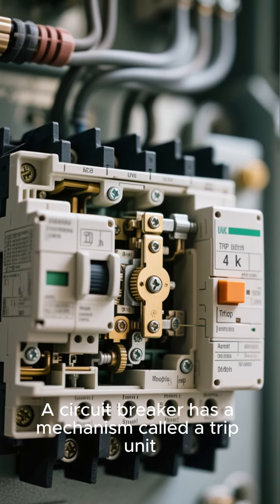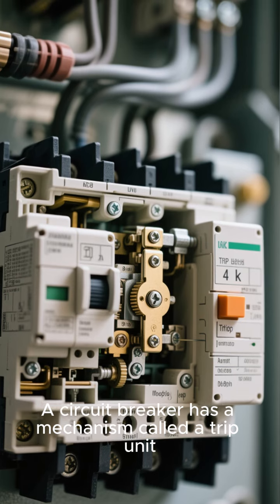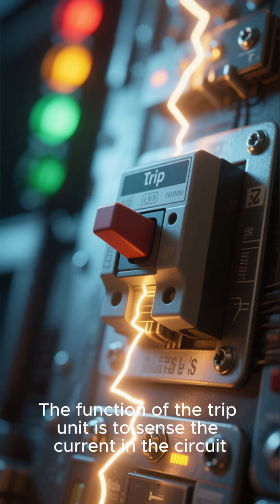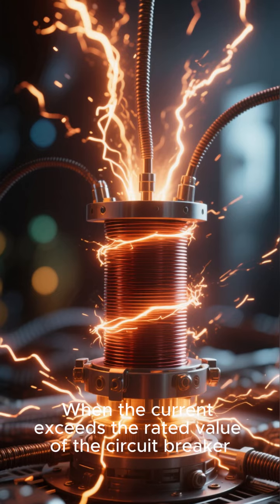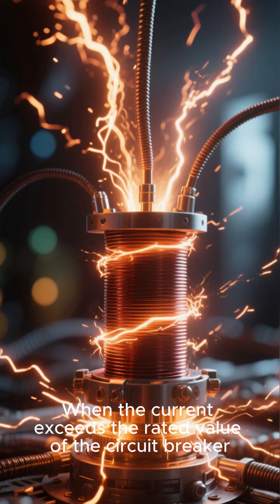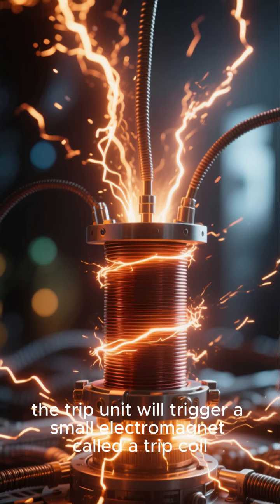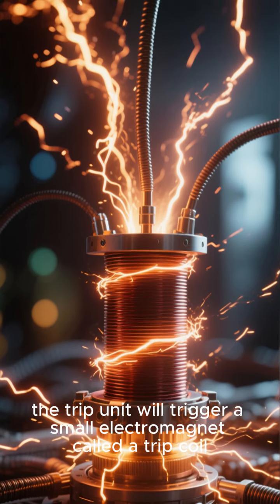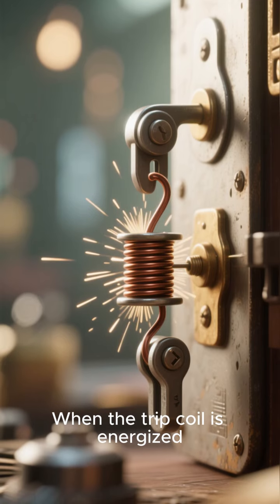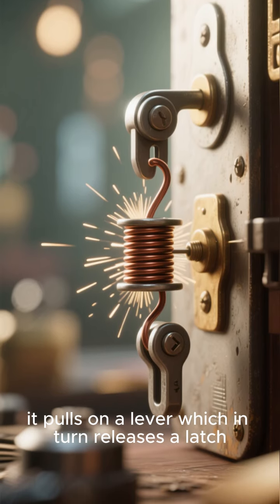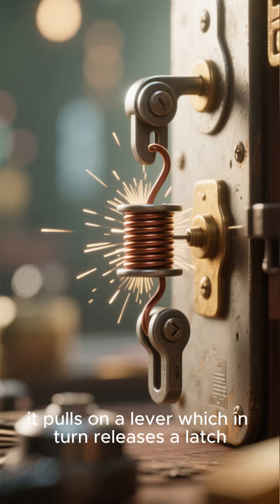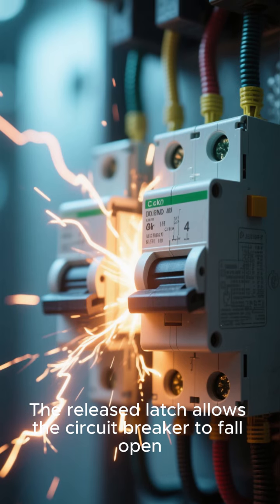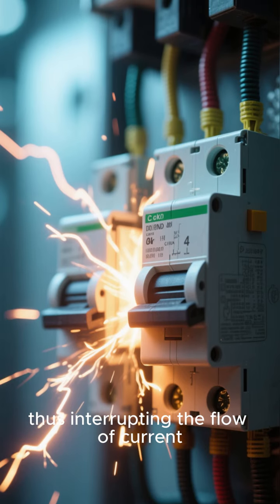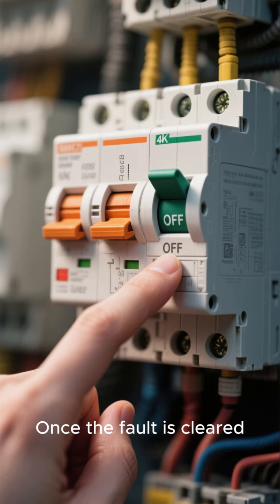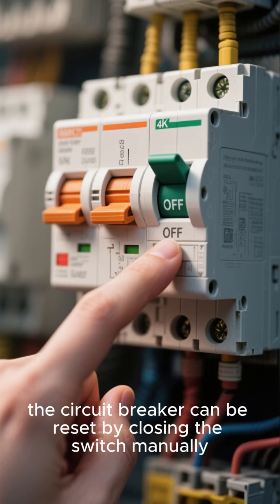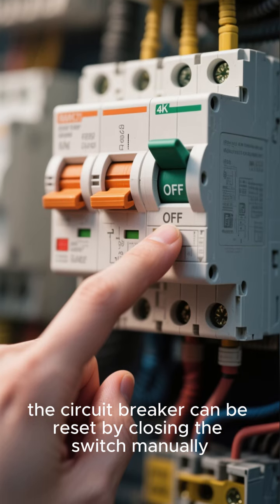A circuit breaker has a mechanism called a trip unit. The function of the trip unit is to sense the current in the circuit. When the current exceeds the rated value of the circuit breaker, the trip unit will trigger a small electromagnet called a trip coil. When the trip coil is energized, it pulls on a lever which in turn releases a latch. The released latch allows the circuit breaker to fall open, thus interrupting the flow of current. Once the fault is cleared, the circuit breaker can be reset by closing the switch manually.